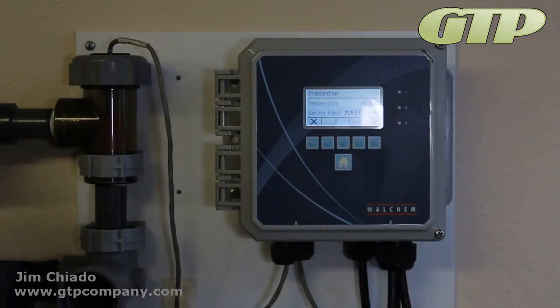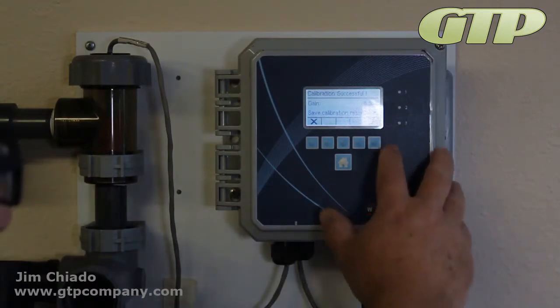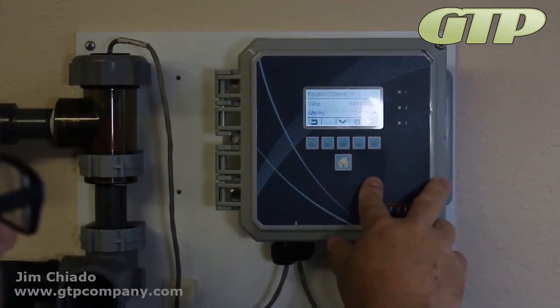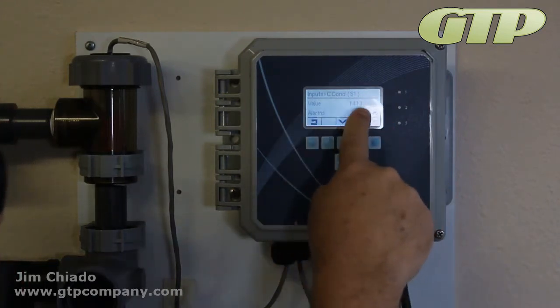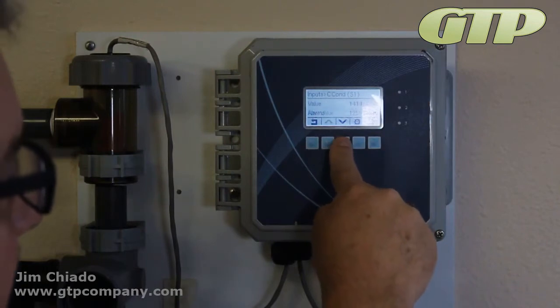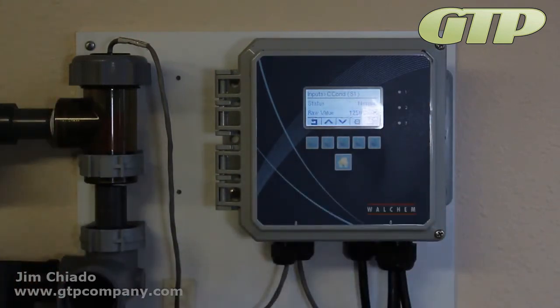That's going to depend on where you're at, and it's not going to give you a true reading. You want to let the machine do the calibration itself. It does take a little while, but we want it right. There we go. Okay, so yes, save the calibration results. Good. Now we're going to go back and look at that raw value. It says it is 1413, but if we pan down, the raw value is 1250. That's the adjustment it makes from what it believes it is to what you're telling it it is. That's when we do a calibration.